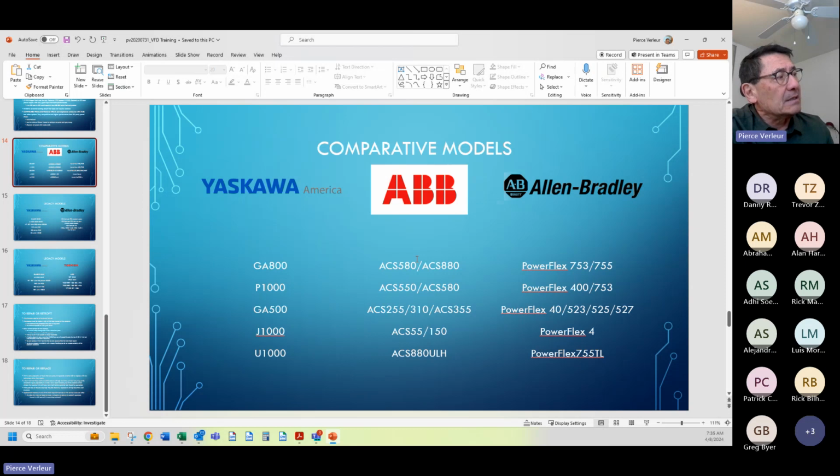The only thing I can say about the ABB product that is a worthy criticism is in heavy-duty, high-cycling applications, such as the oil beam pump, the pump jack, where you're lifting and lowering the rod string every 6 seconds, or extruders and other heavy-duty, high-cycling, dynamic applications.